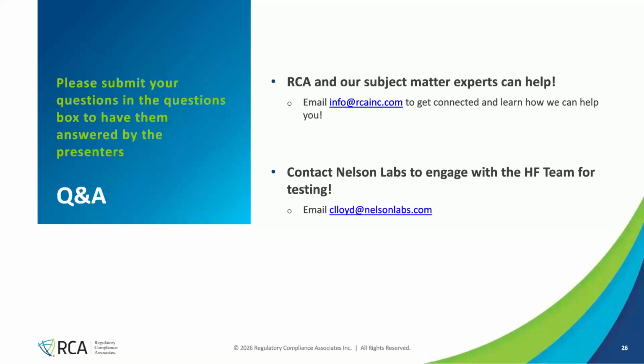So the first question: does the acceptability of the URRA, is it the same as included in the risk management plan per ISO 14971? I'm not sure I understand what we mean by acceptability. A URRA, if it's done specifically in the manner in which the FDA describes it, doesn't completely satisfy 14971 requirements. But if you feed it back into a larger risk analysis, risk evaluation, it can be used as part of your 14971 risk file as a use risk assessment. You need to ensure that you have within the URRA template all of the required aspects of a 14971 risk analysis evaluation. So I think the answer is yes and no.